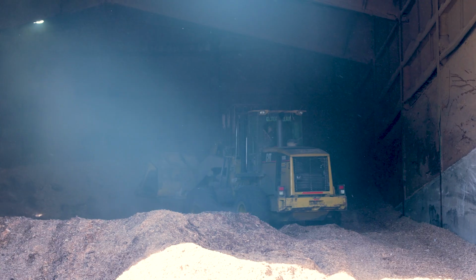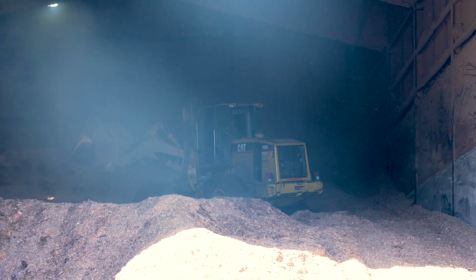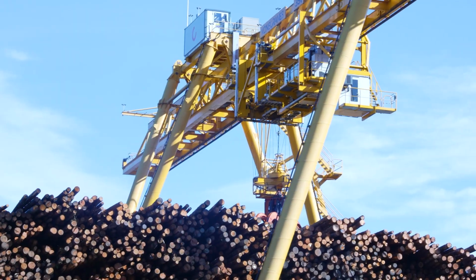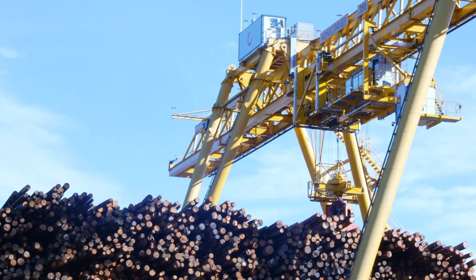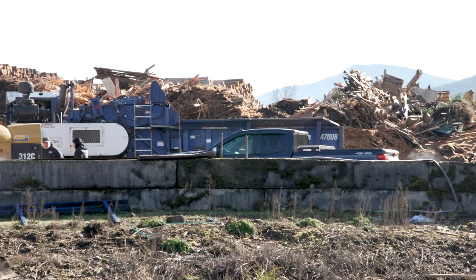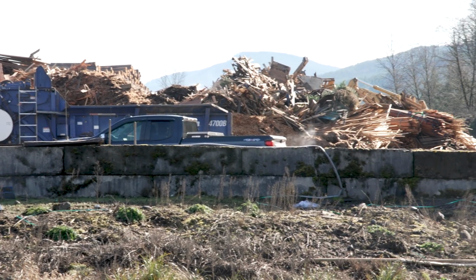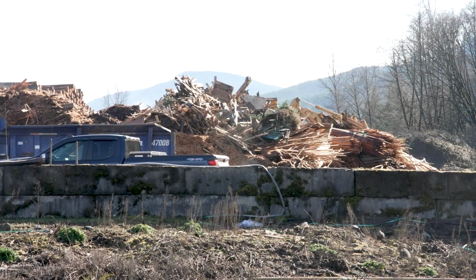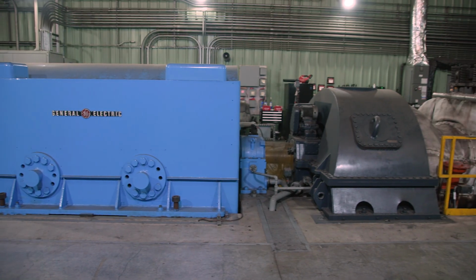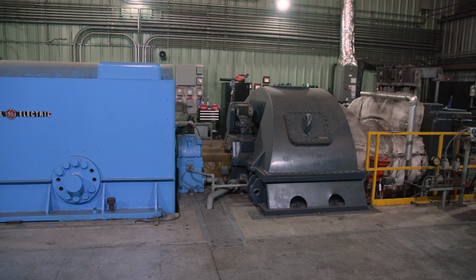We receive about 53,000 tons of biomass waste a year. We process about 20% of that comes from the facility itself, from the grinder pile or from other processes in the facility. With that BTU value we receive from that fuel waste, we produce about 48,000 megawatt hours annually, or 5.9 megawatt hours per hour, which is about enough to power 5,000 homes 24/7.